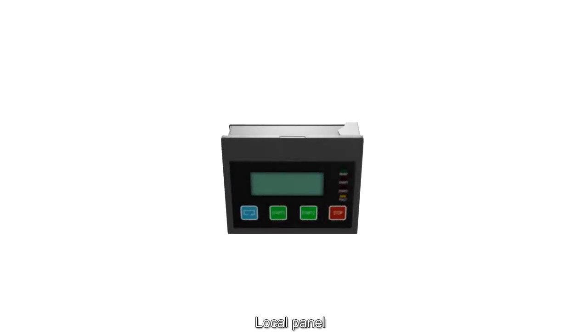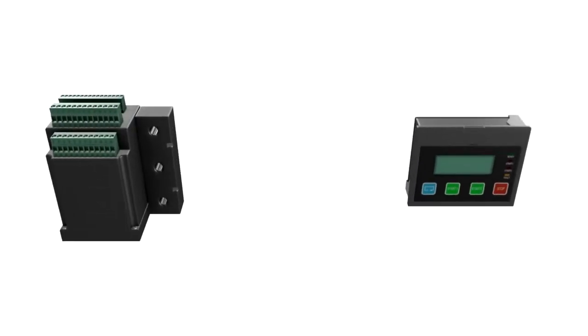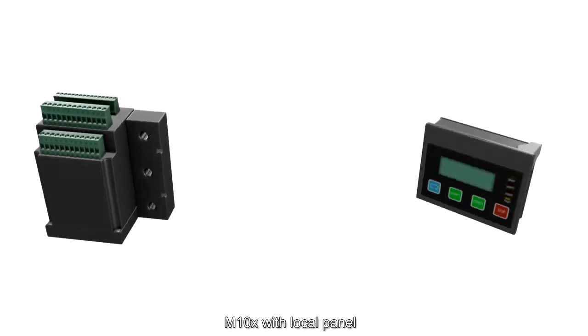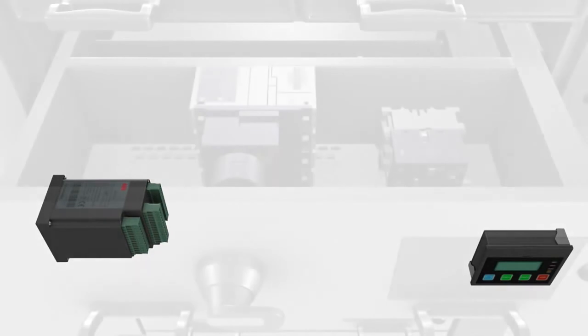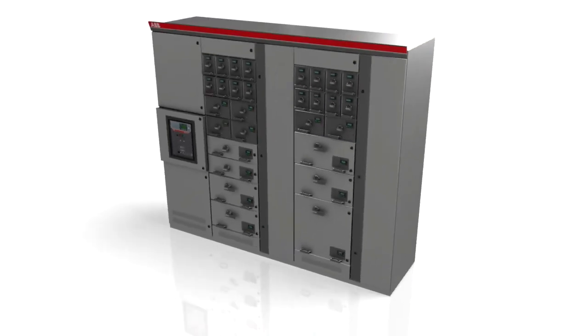The types of devices range from small currents to up to 60 ampere. Larger loads can be monitored using additional current transformer. Different types of Modbus or Profibus communications are also available. They help to minimize the numbers of different starter sizes and provide an easy way to replace a starter unit when required.